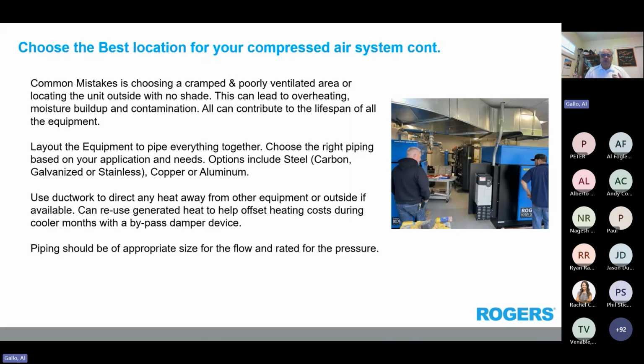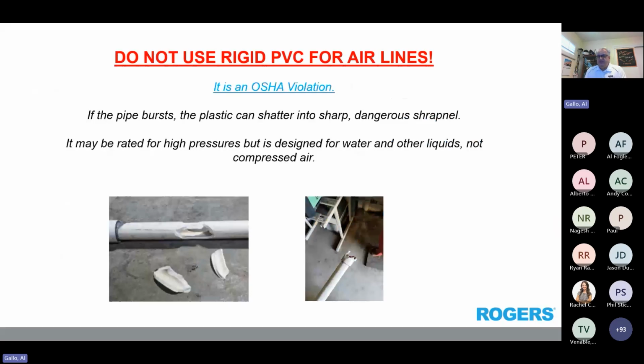And piping should be appropriate size for the flow and rated pressures that you're using. So just make sure whatever you do use, it's appropriate for that. But there is one word of caution. Do not use rigid PVC for airlines. It is not designed for compressed air. There's oils in compressed air that will start interacting with the PVC since it's a petroleum product. I've never witnessed it shattering, but I've seen the aftermath of piping shatter. Shrapnel, people get hurt. It's an OSHA violation. So just do not do that.